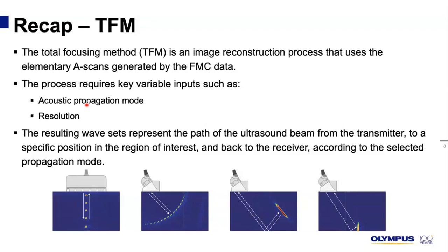The resulting wavesets represent the path of the ultrasound beam from the transmitter to a specific position in the region of interest and back to the receiver according to the selected propagation mode. For example, with a 2T waveset, we expect to pulse, hit something, and then receive. With a 4T waveset, we expect to pulse, skip, hit something, come back, skip, and then go back into the probe.